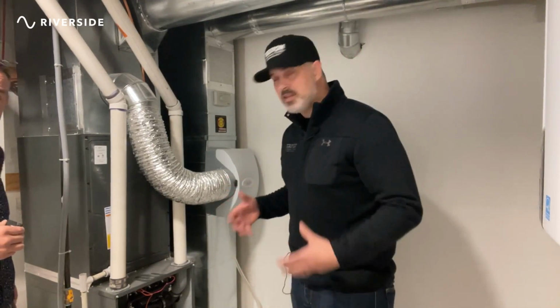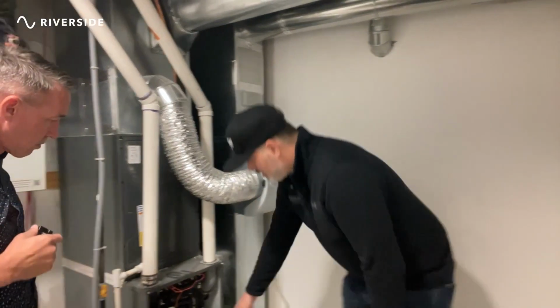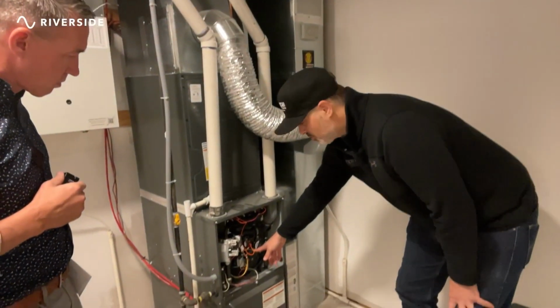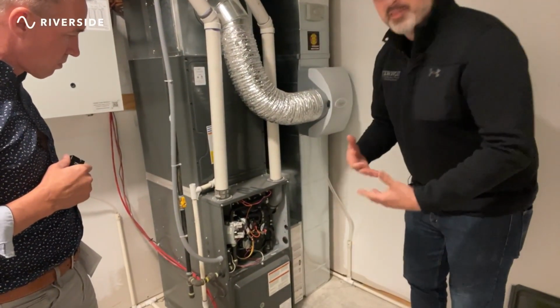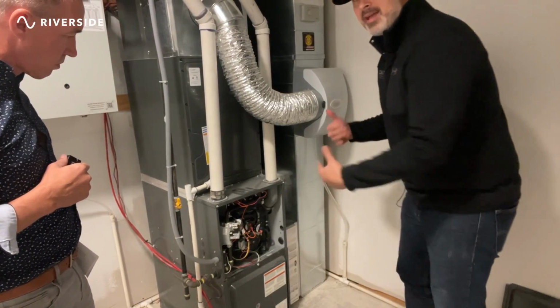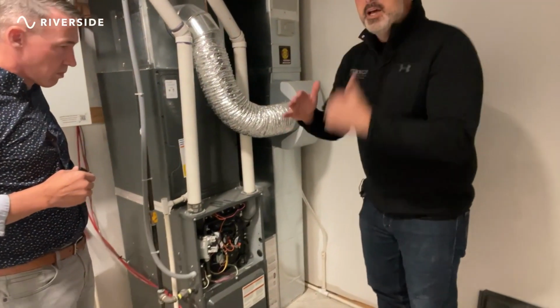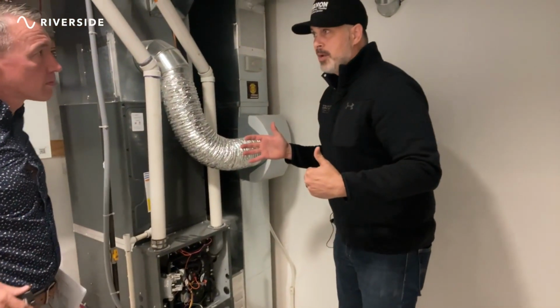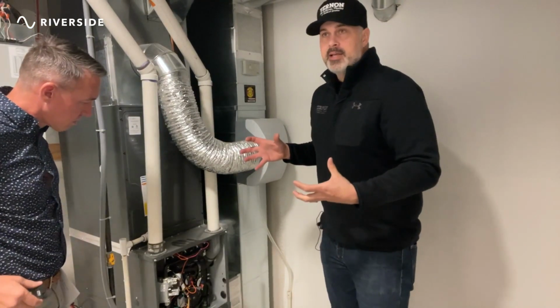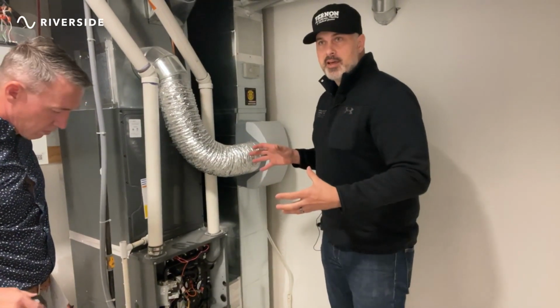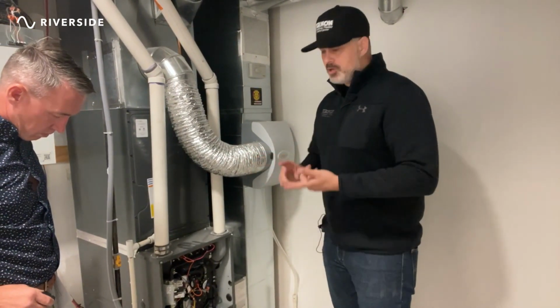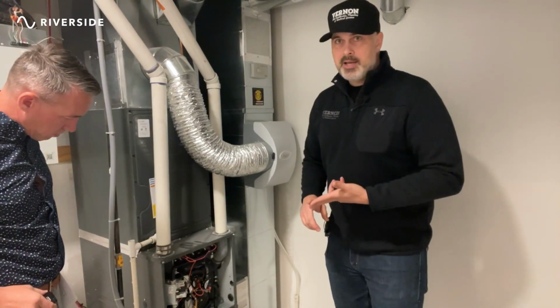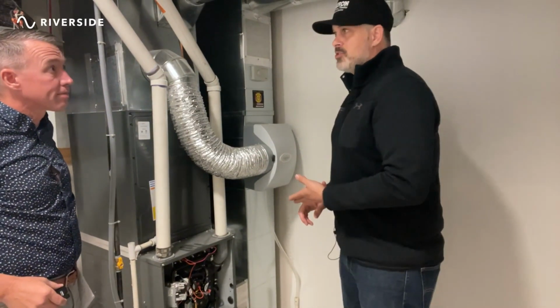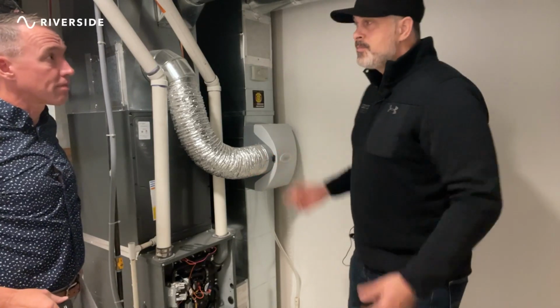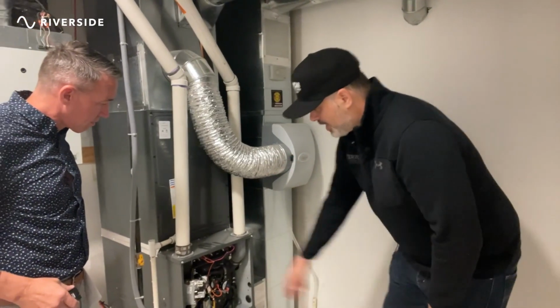But we're checking things like motor amperages. So you've got an inducer motor here. This is your exhaust motor. We're checking the amperage on that, comparing that amperage against the manufacturer specifications. If we're seeing things like it's pulling too much amperage, we're starting to recognize that it's nearing the end of its life. Now, if it's nearing the end of its life, you've got two options. Run it till it dies, or preventatively change it so it doesn't die in the middle of the night. The other thing is checking gas pressures.